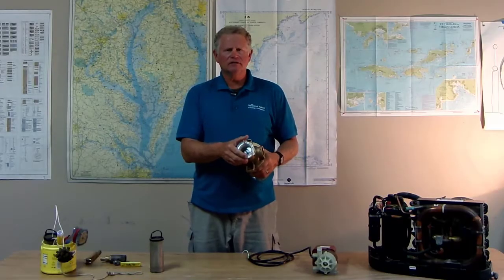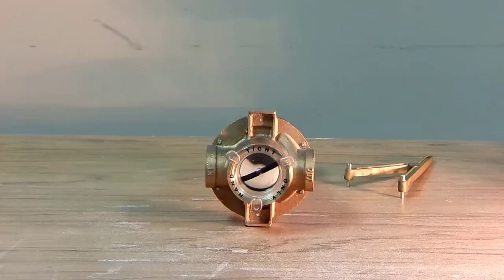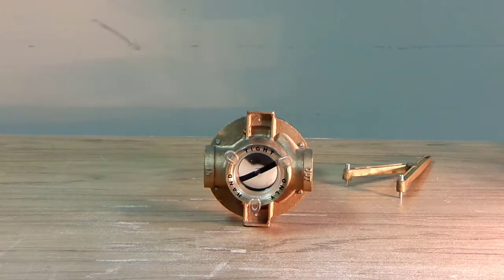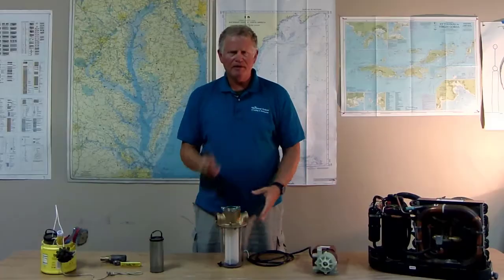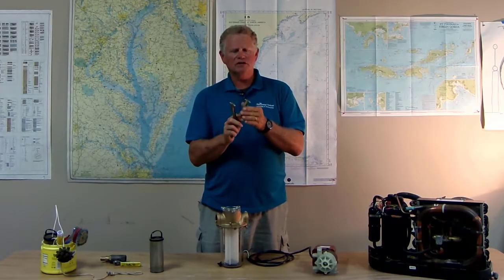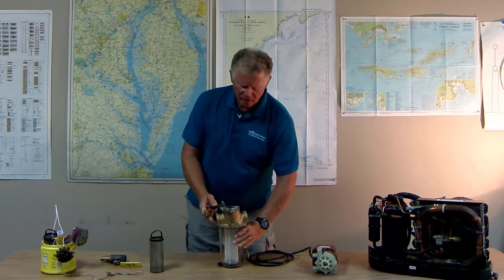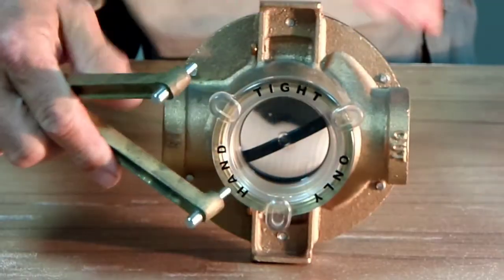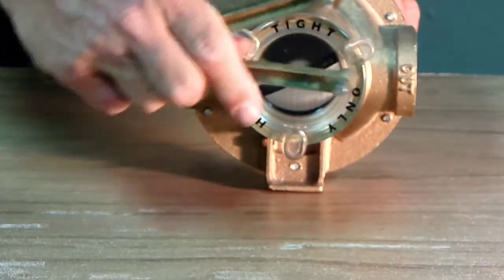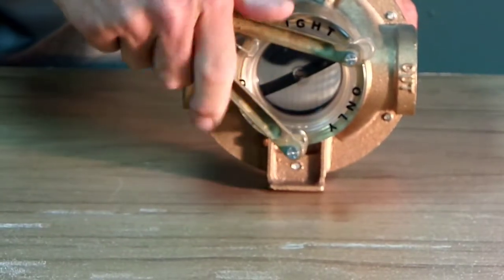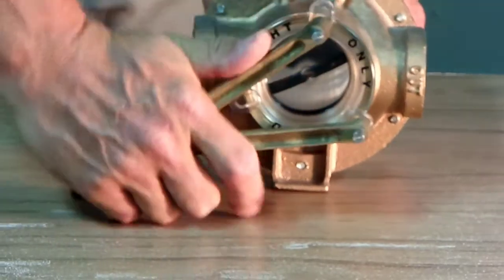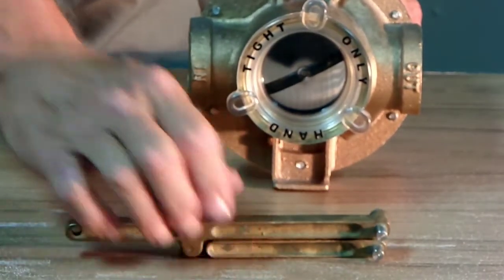In order to clean it, you have to take the top off. The top very clearly says hand tighten only. But it's going to happen occasionally that the system is going to get very tight. If that happens, you need to use what's called a pin spanner to get the top off. A pin spanner has literally 2 pins and an adjustable arm, and we take the 2 pins, put it into any of the 3 holes on the top of the strainer and use it to turn the strainer open.